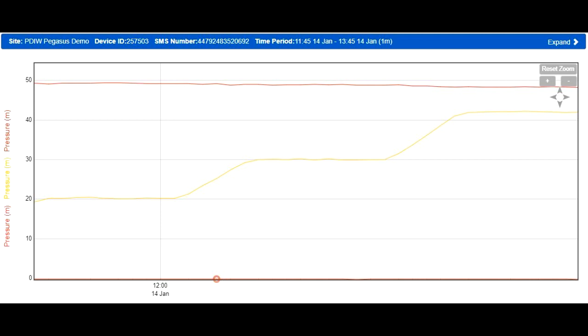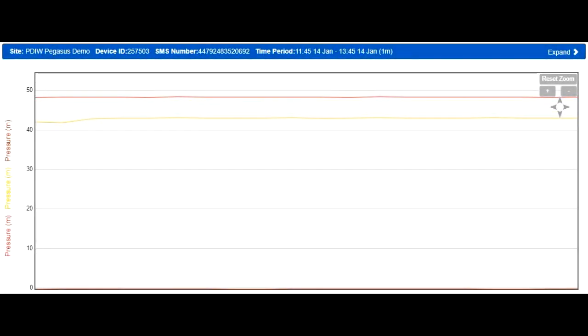Because of its unique feature of linear interpolation, Pegasus is able to create a very smooth interpolation slope between two pressure setpoints. In this graph, we are able to see Pegasus increasing the pressure three times, from 20 meters to 30, and from 30 meters to 42 meters.